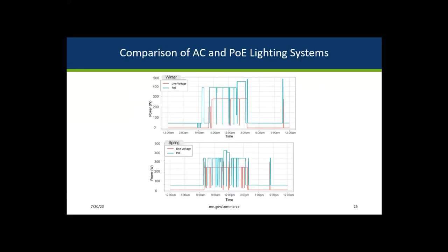Returning to the two classrooms, these graphs show a comparison of the two lighting systems for one day during the winter and another in the spring. In order to assess the energy savings benefit of the network lighting system, the operational savings provided by the network lighting systems should not only show savings compared to the operation of the non-network lights, but also needs to overcome the load incurred by the sensors, controllers, and network devices that run 24/7. In the case of these classrooms, the networked luminaire level lighting system incurs an energy penalty and is not cost effective. This example shows that there is not one size that fits all for intelligent building technologies and systems.